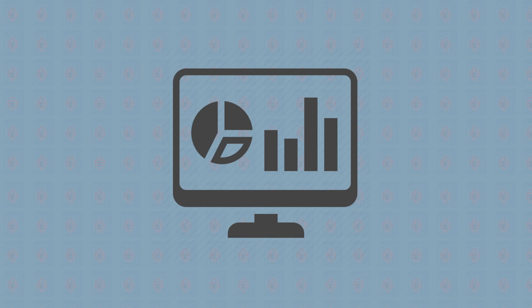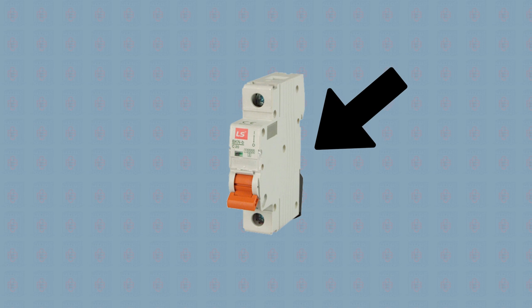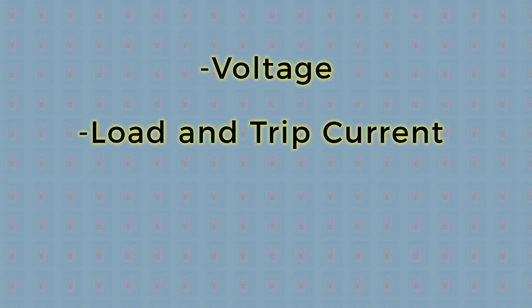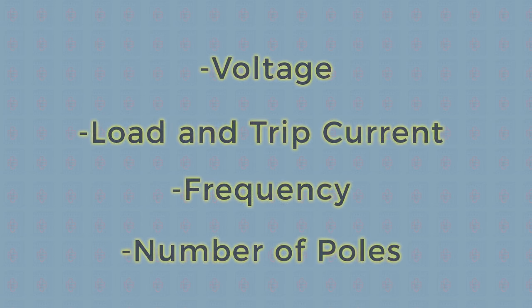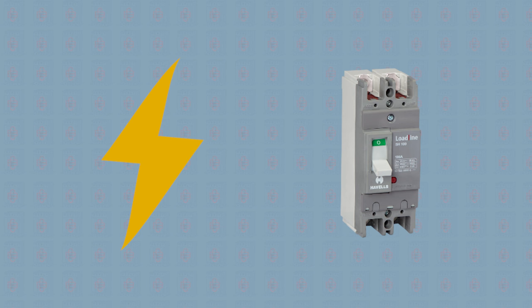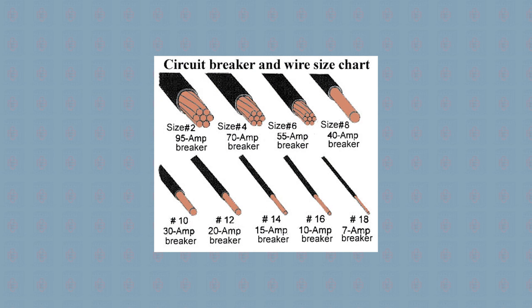Three: check the electrical specifications. You will need to find out a range of specs. If you're replacing an old breaker, you'll find all the info you need on the unit itself. Necessary information includes voltage, load and trip current, frequency, and number of poles. When trying to determine amperage but you do not have an old circuit breaker for comparison, you can use the wire gauge to guide your decision.